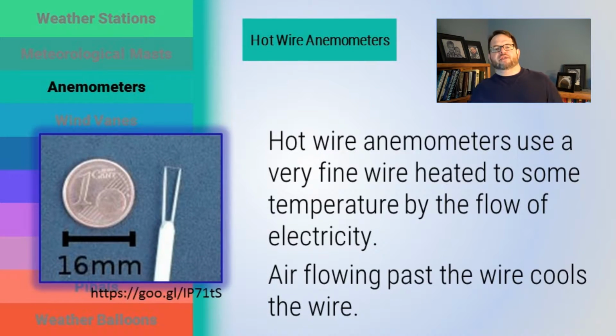But the way a hot wire anemometer works is actually pretty slick. The hot wire uses a very fine wire that is an electrical conductor, and it's heated to some temperature above the ambient temperature through the flow of electricity. As electricity flows through wires, if they are not perfect conductors, they are heated, and they choose a material that will heat up. It'll be a hot wire.